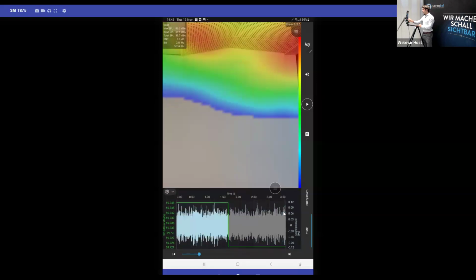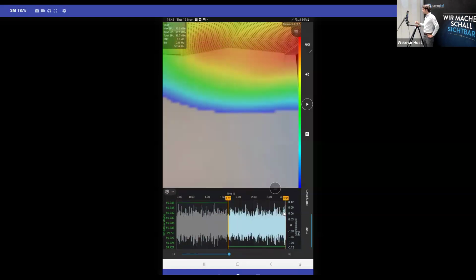So we can see each of these individual frames, or we can choose to average the recording. If I tap on AVG on the top right, I can average the recording. I can select which frames I am averaging. And of course, we can also describe the acoustical image. We see that there are 2 main sources at this stage, one near the corner, and one on the perforated panels near the left of the top.